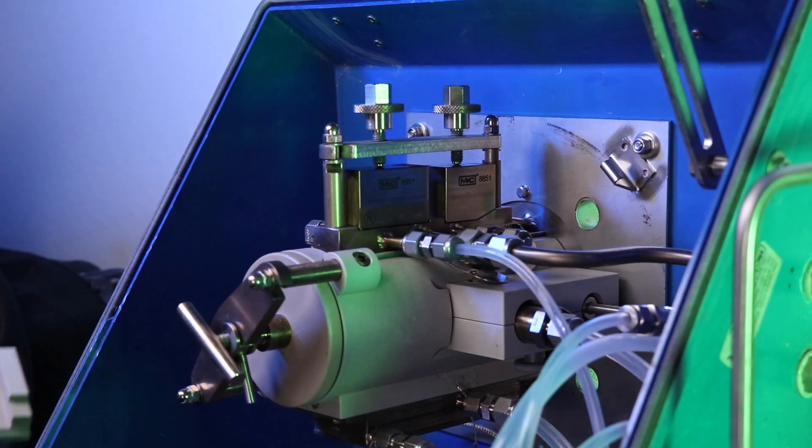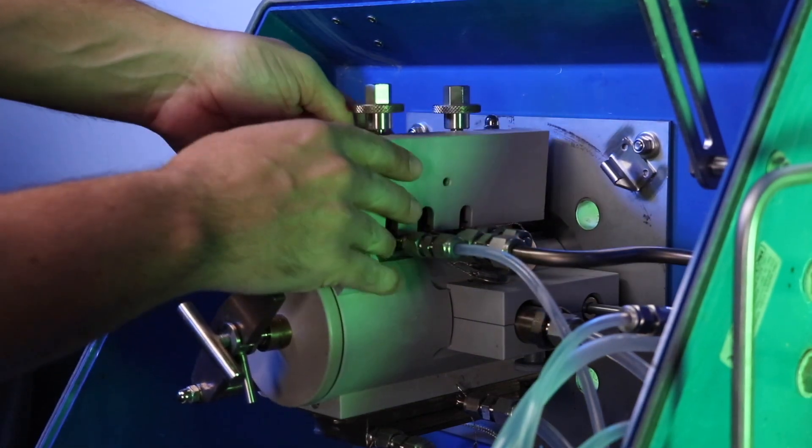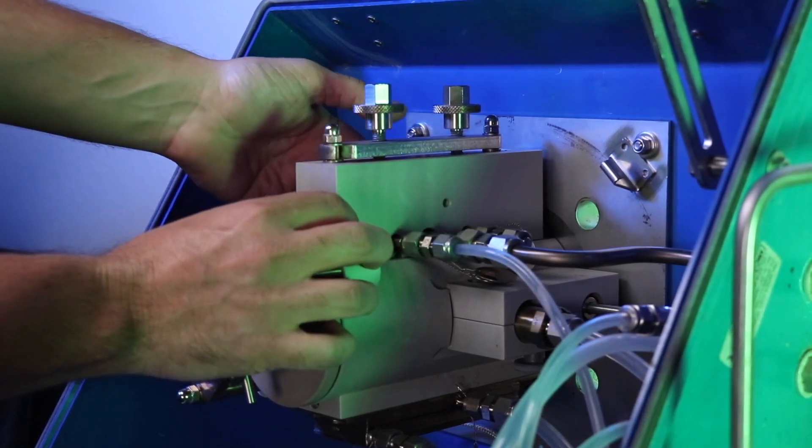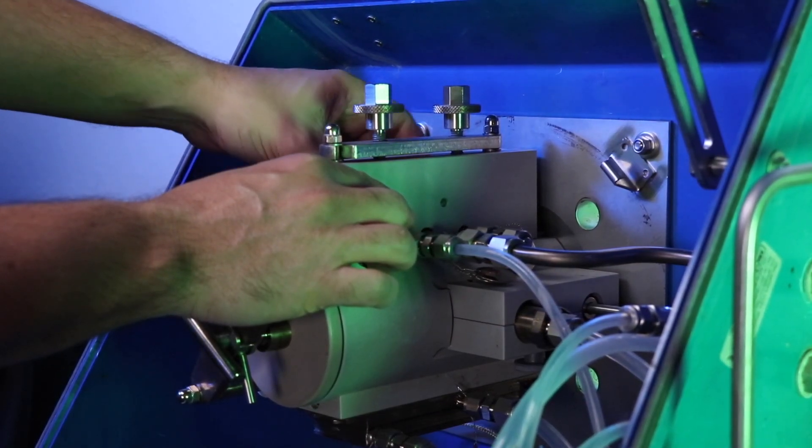Reinstall the thermal conducting jaws, close the clamshell case, and you can now return the unit to normal. Run calibrations to verify your repair was successful.